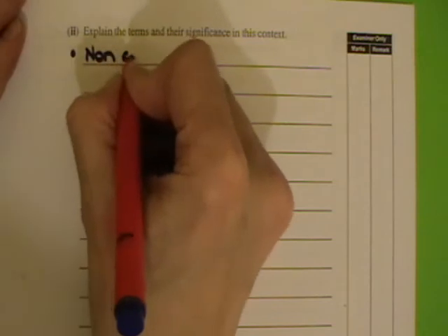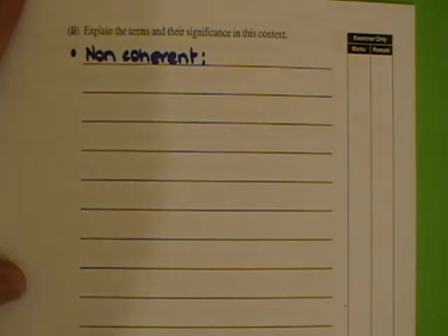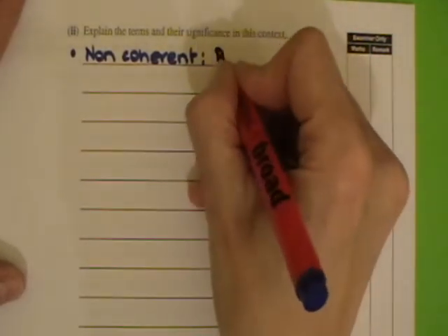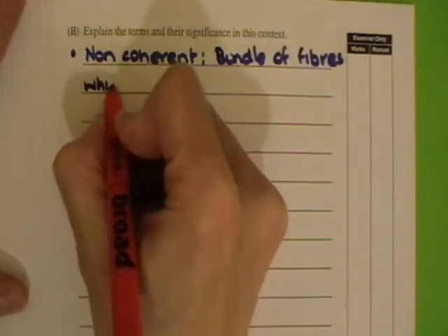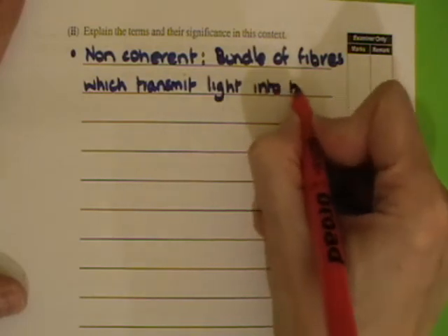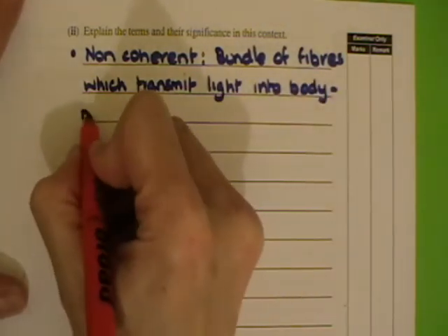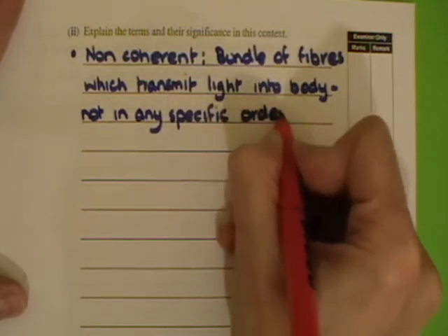Explain the terms and their significance in this context. We'll explain non-coherent first. What that means is that the bundle of fibers along which the light passes into the body aren't in any specific order, because it doesn't matter where the light comes from when it gets down to the body — as long as the light is being passed down, say to illuminate a stomach ulcer. So this is a bundle of fiber optics which transmit light into the body, and they are not in any specific order. The word 'order' is very good to use there.